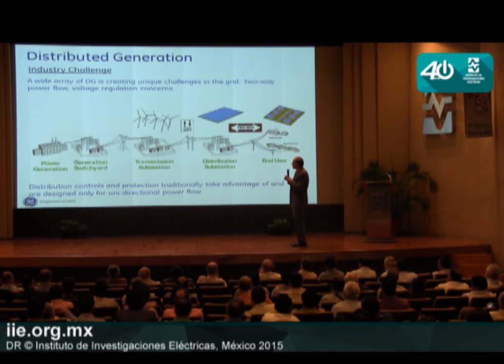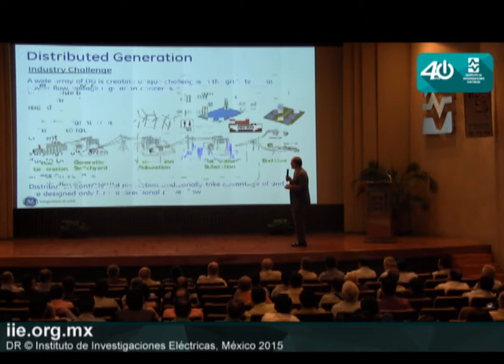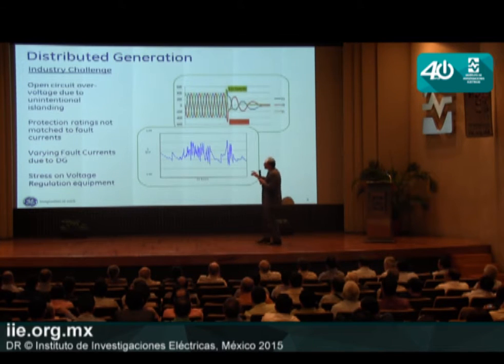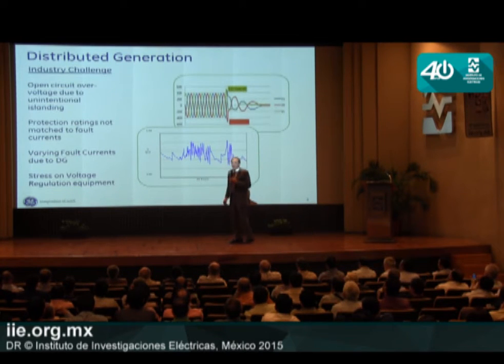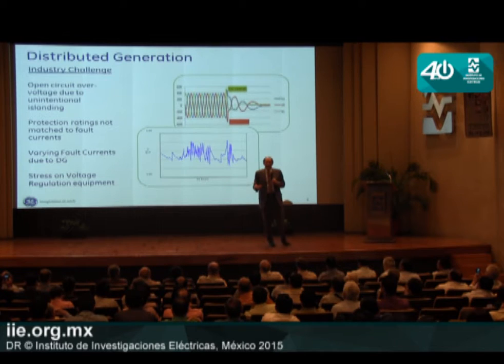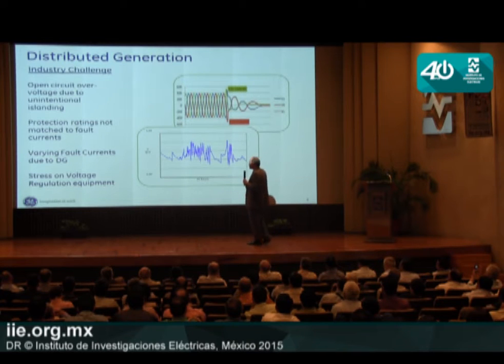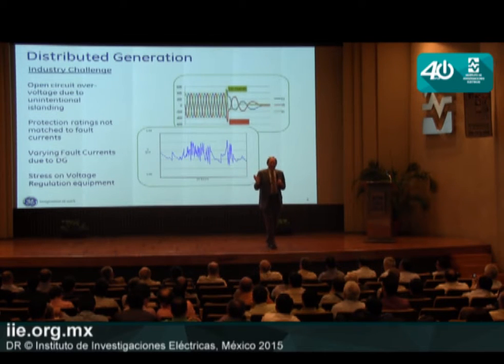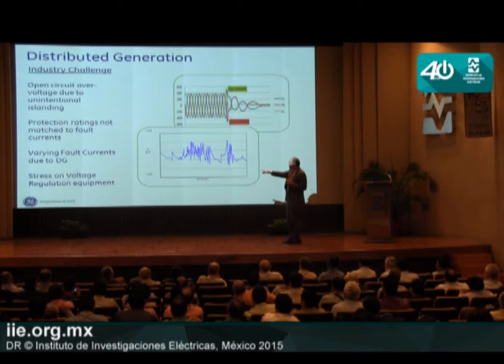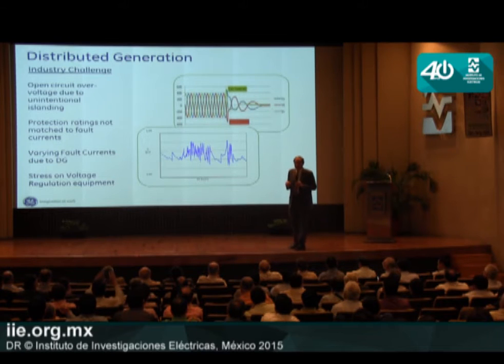So what are some of the challenges that renewables give us? One is open circuit overvoltage due to unintentional islanding. Protection ratings may not match fault currents because our rating was based on the contribution from the source only - now we have a load side contribution. Fault currents vary as the wind or sun changes, so the contribution from the renewable to a fault will vary, giving us varying fault currents due to distributed generation, and stress on voltage regulation equipment. I want to talk more about that with a specific case study in California.